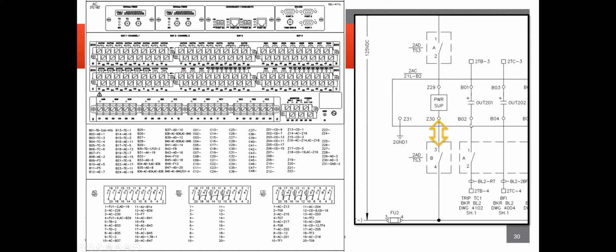Moving on to identifying the wiring from the DC schematic to the actual wiring diagram itself. Say you have an issue between the power supply of the relay and the associated test switch. In this case, it would be the Z30 contact on the back of the relay going to the test switch number three contact. If you had issues there, you want to identify each piece of equipment to begin with, where the issue might be, and then move on to the wiring and identify it there.